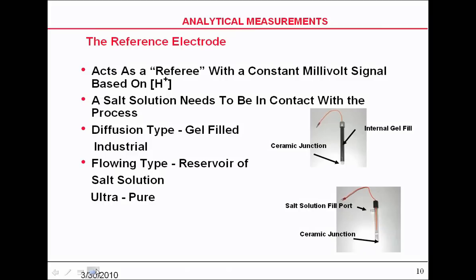The salt in it is needed to make contact with the process and also to make contact with the measuring electrode. In the industrial type, we use gel-filled. The reason for that is it's harder to contaminate it. It's slower to migrate. We don't need as much reference electrode in industrial probes as we do in ultra-pure for DI water manufacture or for ultra-pure in a power plant.